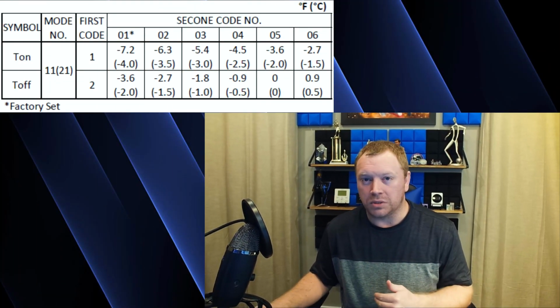during defrost. The last set of settings you're going to need to program are what we call the T on, T off settings. Basically, it's the number of degrees you want to let the room temperature drop below the set point before the strip heater comes on. And then after it comes on, how many degrees you want that strip heater to help recover the room temperature to before it shuts back off.